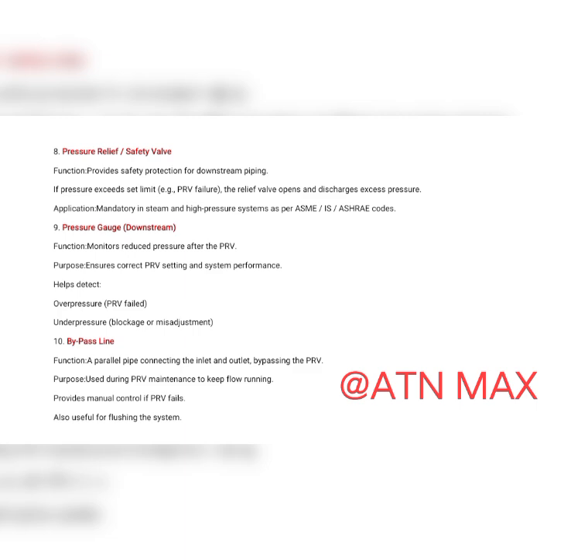ASME/IS/ASHRAE codes. 9. Pressure gauge, downstream. Function: monitors reduced pressure after the PRV. Purpose: ensures correct PRV setting and system performance. Helps detect overpressure, PRV failed. Underpressure, blockage or misadjustment.